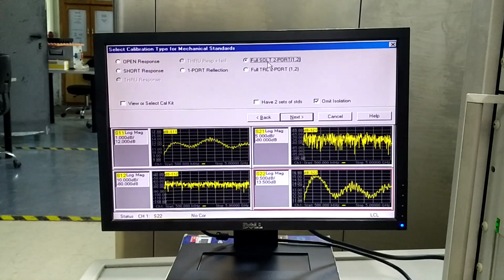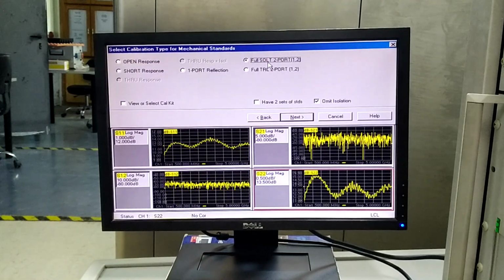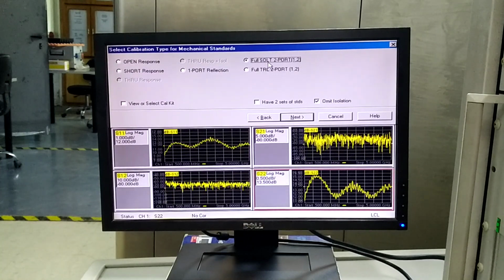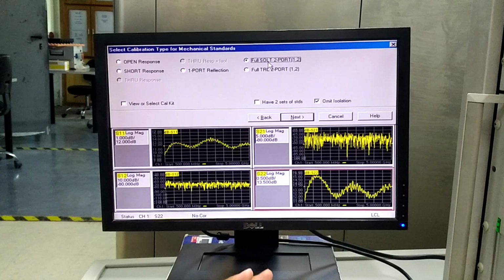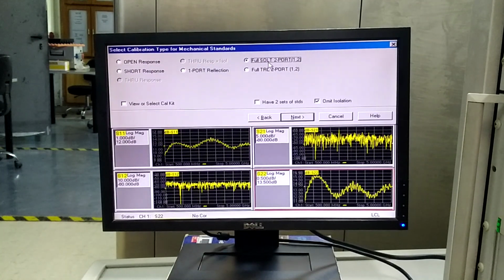So this is particularly used for the VNAs, for example a two-port VNA, that have two measurement receivers and one reference receiver. So the number of errors that are generated from the VNA is 12. However, if the VNA has two reference receivers and two measurement receivers, the number of errors reduces to 7. So in that case, instead of performing a full SOLT calibration, you perform a SOL and unknown thru calibration. That may be useful to solve that particular case. But for our case, we're performing a full SOLT calibration.